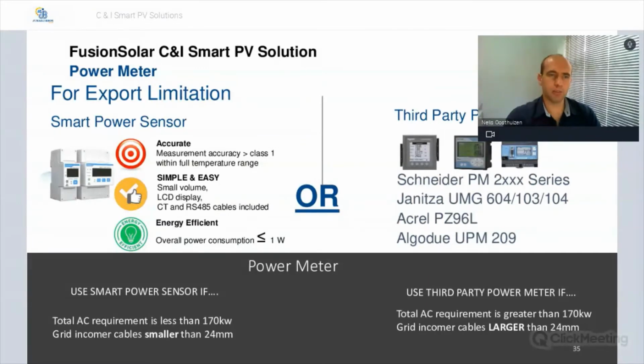So moving over to the power meters. For export limitation, if you want to add this function, or if it's a requirement by your country as a law where you're not allowed to export any excess power generated by your system into the national grid, then you have to make use of a smart power sensor or a third-party power meter. Going into the details, the Huawei specific smart power sensor is for an AC requirement of less than 170 kilowatts. So if your system is smaller than 170 kilowatt, then you can make use of the Huawei system. And also make sure that your grid incomer cables are smaller than 24 millimeters.